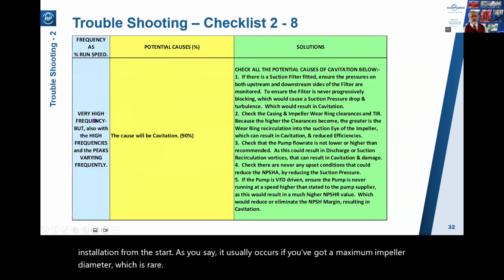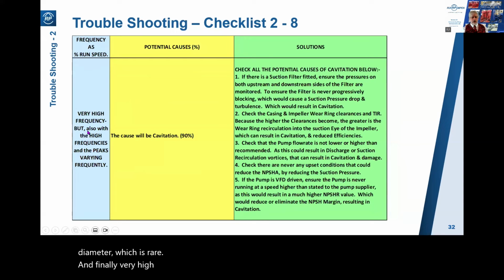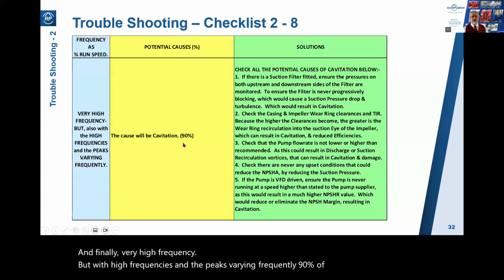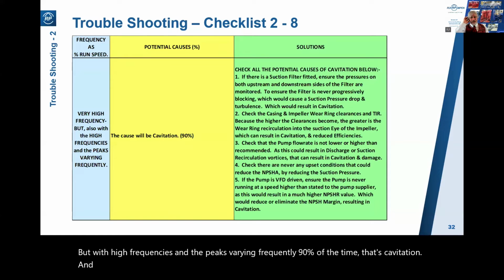And finally, very high frequency, but with high frequencies and the peaks varying frequently, 90% of the time, that's cavitation. And again, you'll have the acoustic sound. You'll hear the sound of gravel in your pump, effectively.